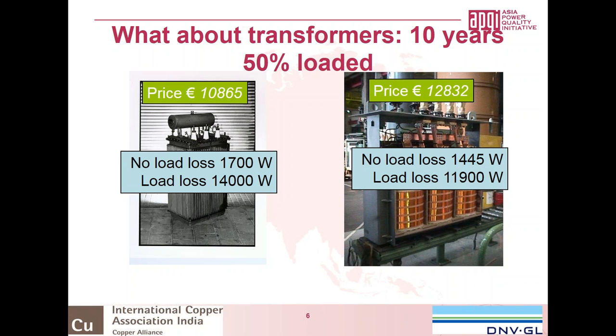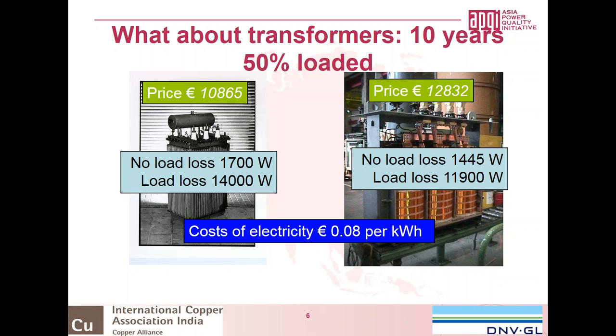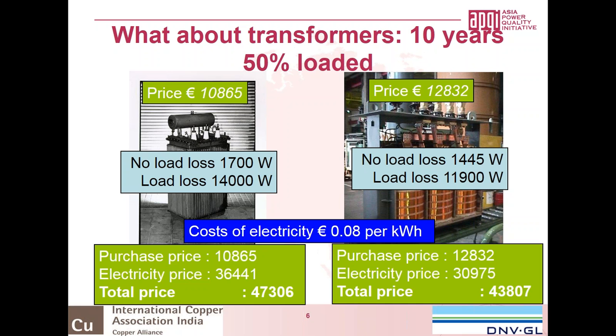Both of them have a price, and you can imagine that the transformer with low losses normally has a higher investment price because you need more material in it and those kinds of things. So in this case, the transformer on the right has a higher price compared to the transformer on the left side, which has higher losses. But let's assume that you want to use the transformer for 10 years and it's 50% loaded. Then you need, of course, to know your electricity price. I assume about 8 euro cents per kilowatt hour. And then you can calculate the total effect, of course.